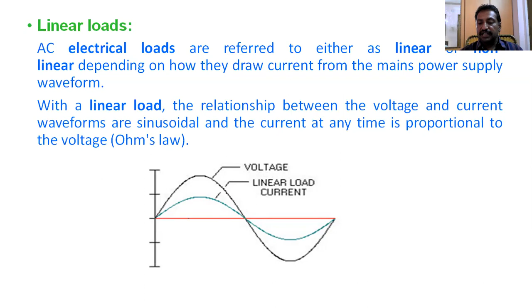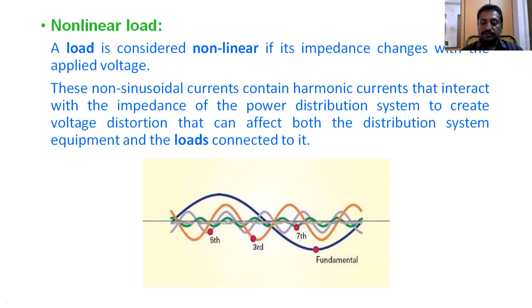In non-linear loads, the load is considered non-linear if its impedance changes with the applied voltage. It changes immediately. These non-sinusoidal currents contain harmonic currents that interact with the impedance of the power distribution system to create voltage distortion that can affect both the distribution system equipment and the loads connected to it. So this is about the non-linear load.